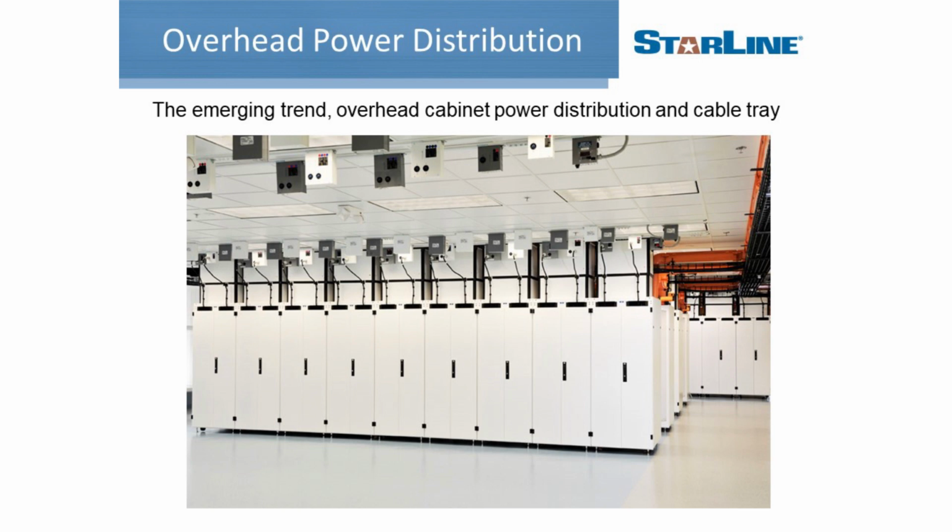What you see here, we continue to see an emerging trend going to overhead power as well as no raised floor. In this scenario, this was a joint installation, another joint installation we did with Chatsworth, where no raised floor was deployed. And chimney cabinets were also integrated here for exhausting the hot air into the plenum above the ceiling. Also, the end user here utilized different colors of the plug-in units to designate between A and B.